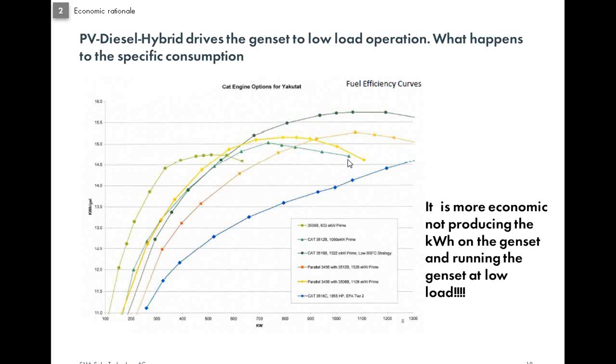So if you can follow the green triangles, this is for a particular inverter we have chosen, diesel genset brand we have chosen, and you can see that the efficiency of this genset would be slightly lesser than 15 units per gallon. Now this genset was working at 30% load, 300 kilowatt. So this is a 1 MVA genset. If it was operating at 300 kVA, then its efficiency would be close to 13.5 kilowatt hours per gallon. So earlier it was 15, now it is 13.5.